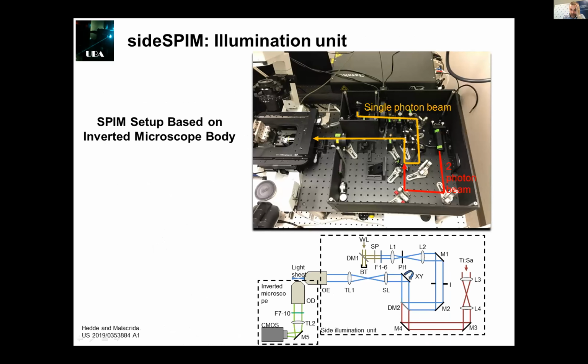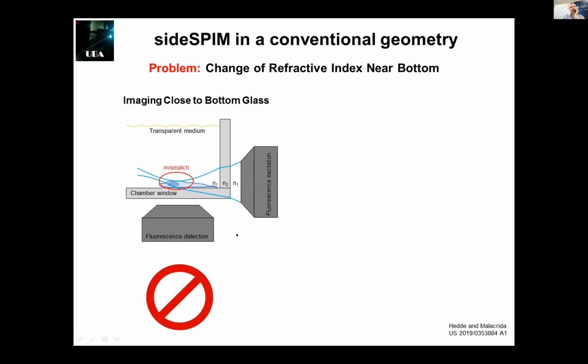We can do single photon excitation. In this configuration here, we were using a white light laser, so we need to have different filters. We have a filter wheel here in order to select the different bands. And then we have some sort of pinhole and other optics in order to clean up the shape of the beam. Then our combination between the two photon and the single photon excitation, our scanner, the scanning lens, and then our objective here, and the emission objective here. So this is a very easy and very cheap configuration to do on an existing epifluorescent microscope like the one that we have here.